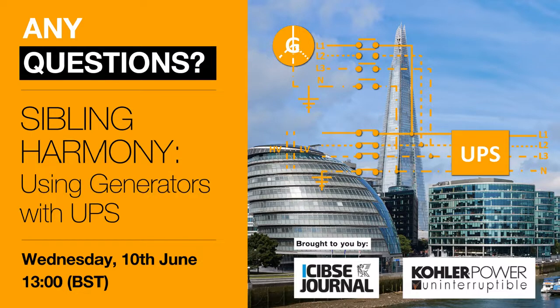Typically, you wouldn't do it with a UPS, although it's physically possible. But with generators, yes, you could have a large generator plant that feeds different buildings with separate substations. We also see that inside a lot of buildings that have more than one intake. So the generating plant will supply the whole building or part of the building, depending on if one or more of the supplies fail.